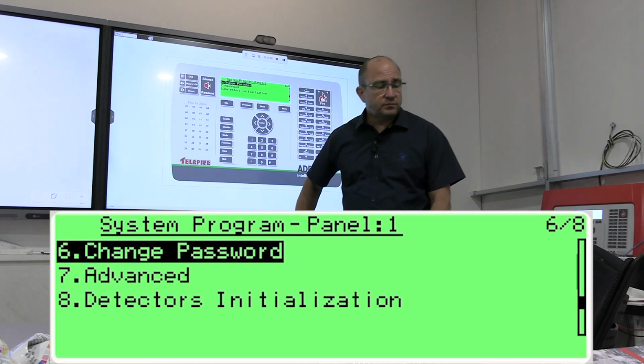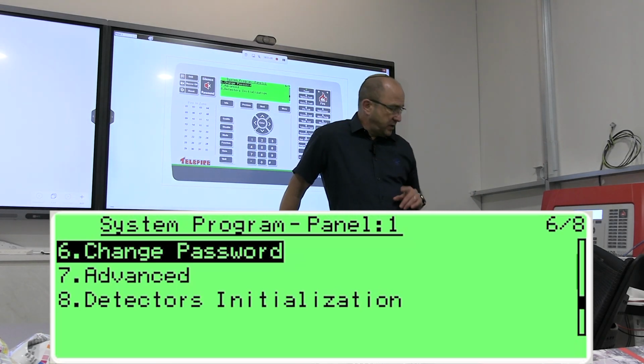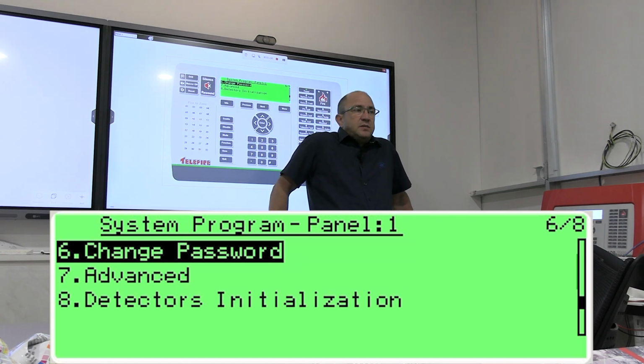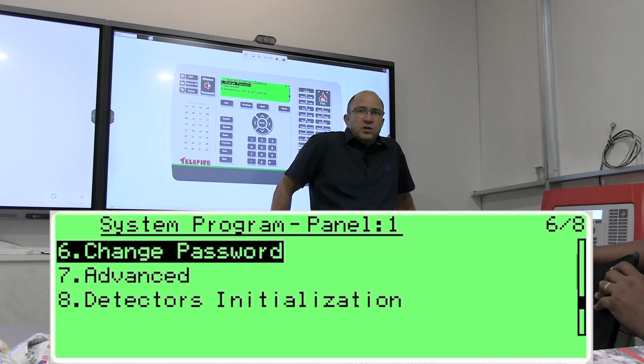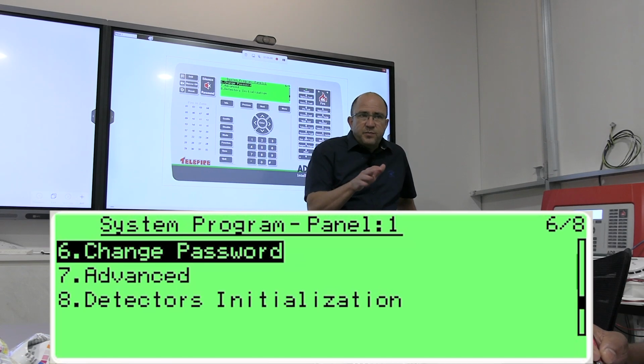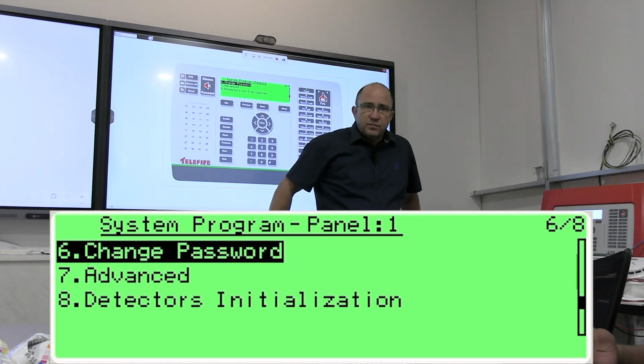Change password. Listen carefully about change password. I said there are 6 passwords. The first 3 belong to the operator, the end user. 6 times 1, 6 times 2, 6 times 3. Like I told you before, 6 times 1 is a very simple, stupid one. All it can do is silence. That's it. You don't have to change it.